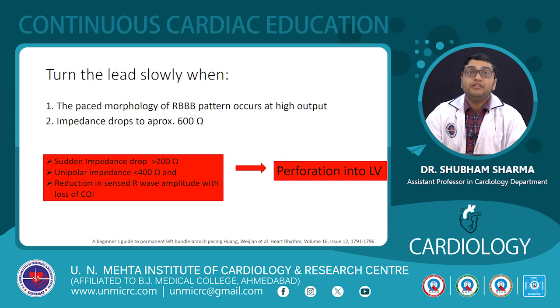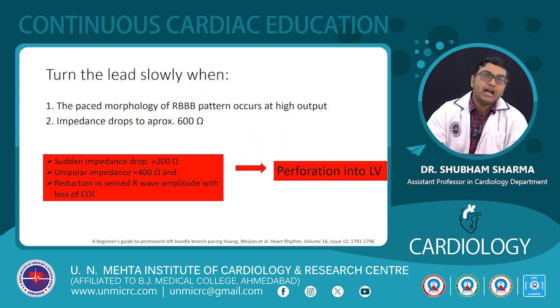So when should we be cautious? When the paced QRS morphology of RBBB pattern comes and the impedance drops to approximately 600 ohms, at this situation we should be very careful in screwing. So now we should screw only half turns. And suppose the sudden impedance drop is more than 200 ohms, or the unipolar impedance falls to less than 400, and there is a sudden reduction in R wave with the loss of current of injury, you have actually entered into the LV. In most cases, LV perforations are not dangerous. We can reposition the lead. However, we don't know when it will be fatal.